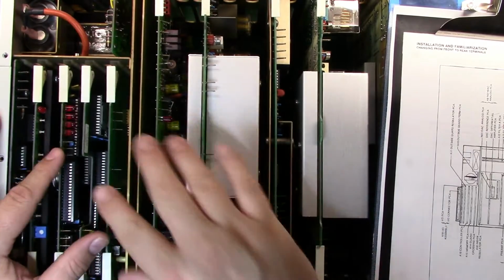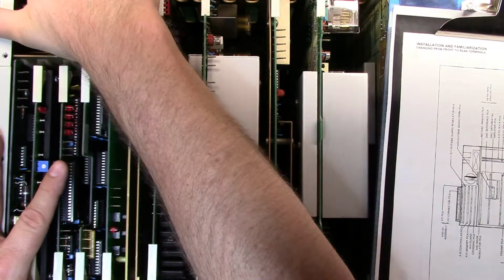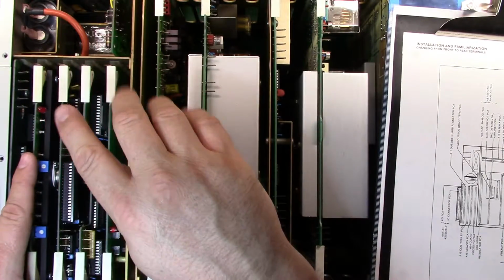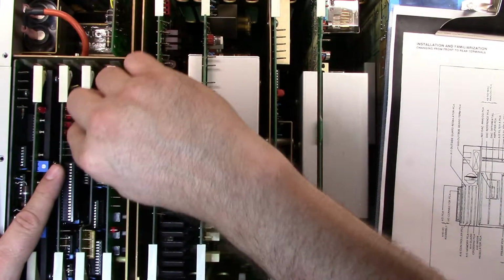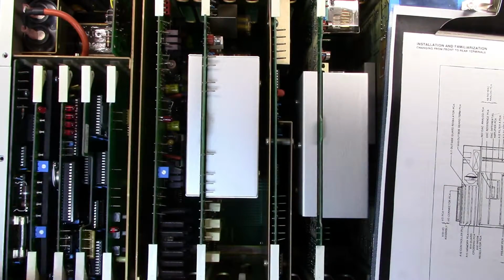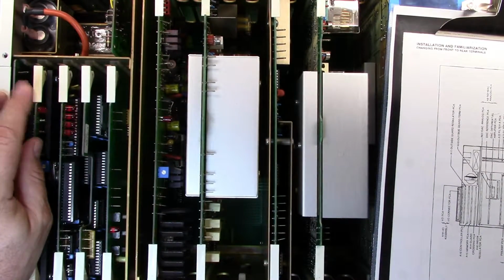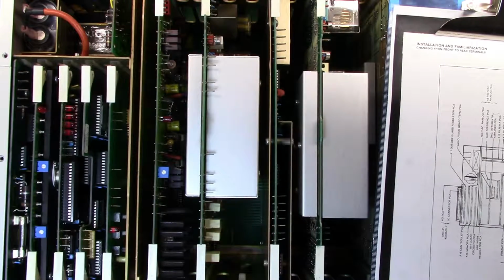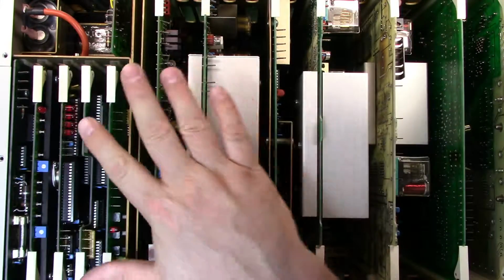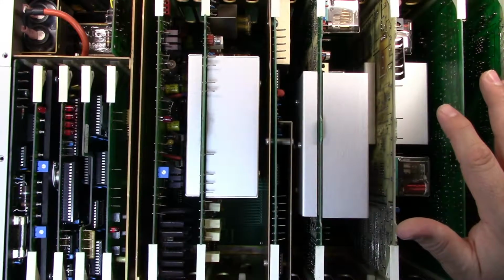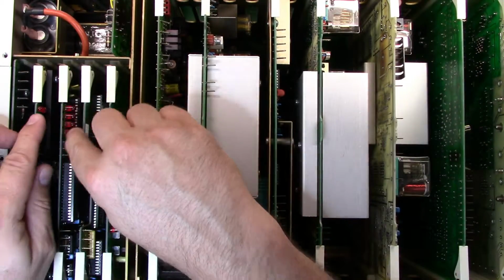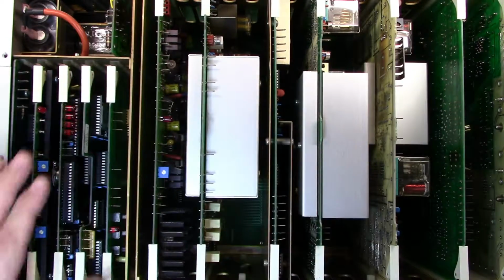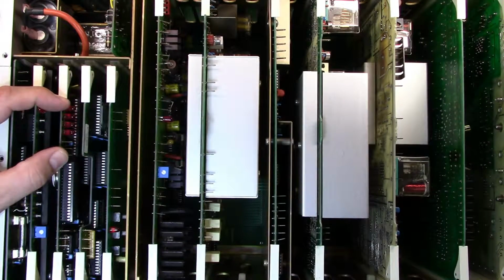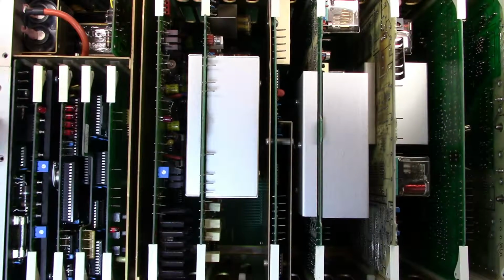In my previous unit, what I saw is that if there's no problem with the power supply, it should start cycling through these LEDs, and CR12 should never light up. But if there's a problem with one of the other boards, it will light up and the cycling will stop. If that process works, I know the microprocessor part of controlling the system is fine, and if this light comes on, I know it's a power problem.